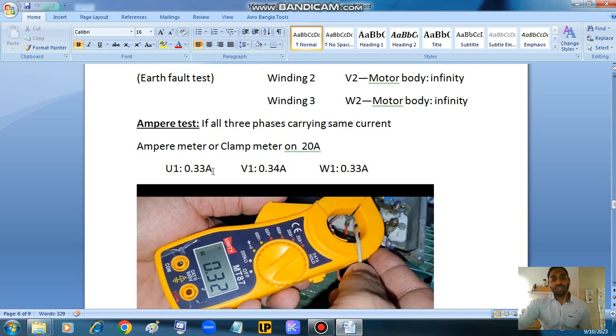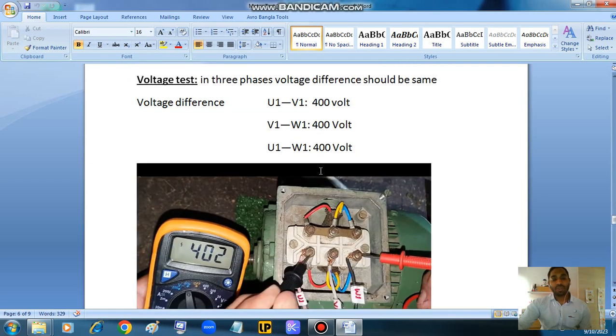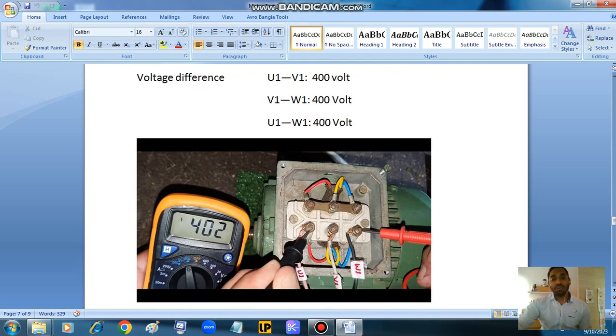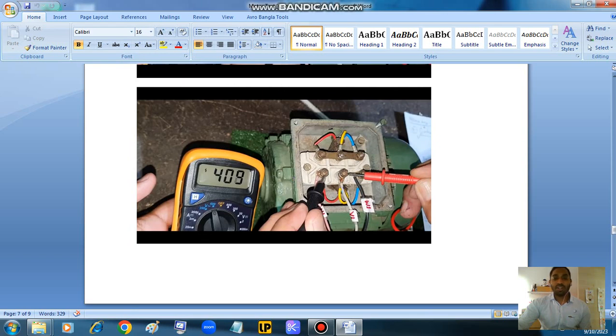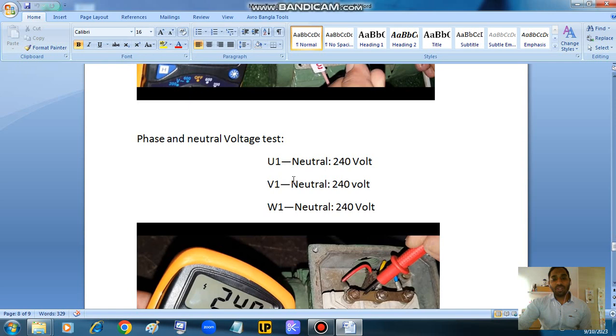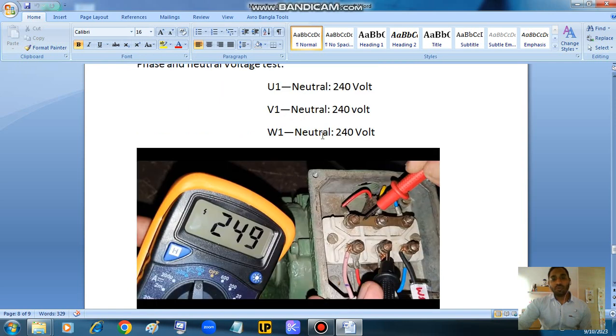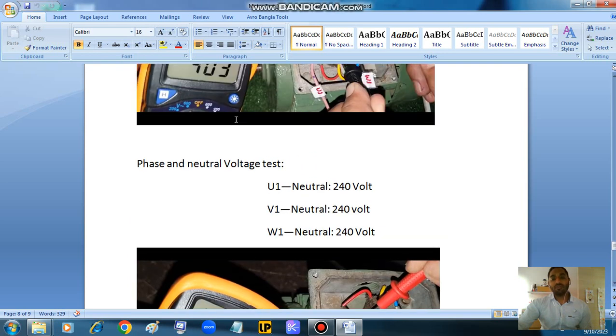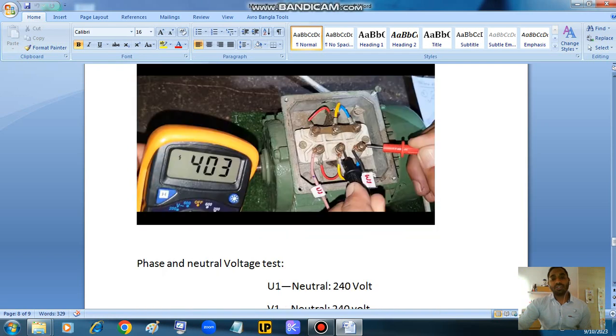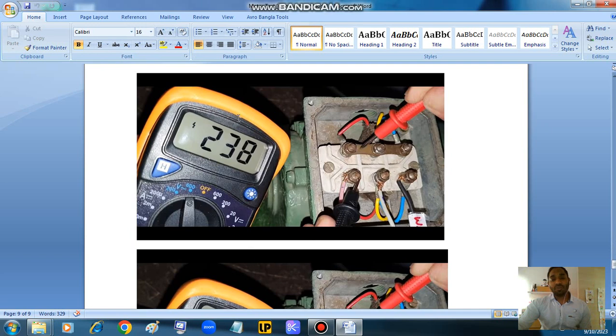We have here 0.33 ampere, 0.34 ampere, but they're almost the same. Voltage test: in three phases, the voltage difference should be the same. Between U1 V1, V1 W1, and U1 and W1, we have here 400 volts, depending on the supply you have. For the voltage test you can also measure U1 to neutral, V1 to neutral and W1 to neutral. If the motor is connected in star connection, you keep one probe of the multimeter here and the other probe once on U1, then V1, then W1, and you get 240 volts here. On the motor we have a plate where the parameters or data of the motor are written: the connection, the voltage, the ampere, the current consumption, and the resistance of the windings.